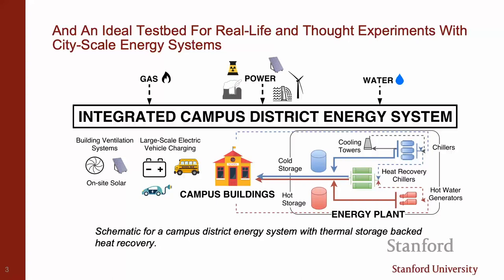We also have storage — big tanks. If you've driven or biked next to that building, you'll have seen the tanks; that's most of the footprint. There are tanks for hot water and chilled water. The heating and cooling is sent to the buildings through pipes — what's called a district energy system, both district heating and district cooling. There's roughly 10 miles worth of pipes for each system. In 2016 when we upgraded the system, a big part was ripping out the steam pipes and moving to hot water.